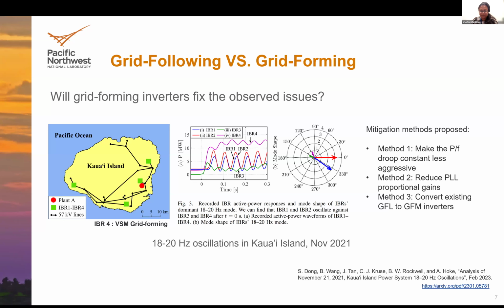So here is an example, and this analysis was done by NREL, and I have put a link to the papers and the presentations on the slides as well. And this is observed in an island system, the Kauai Island in Hawaii. They had 4 IBR plants, and again this one is pretty recent. It was reported in November 2021. There was a loss of generation of about 20 to 30% of the island's generation that was being provided by one synchronous generator plant.